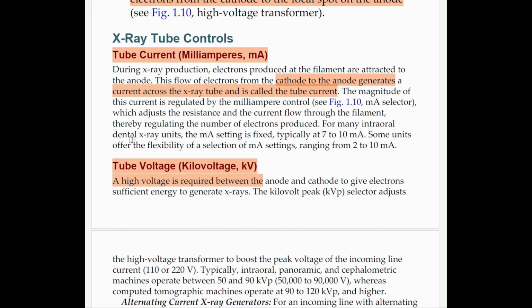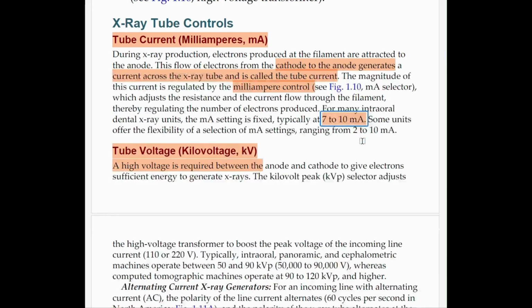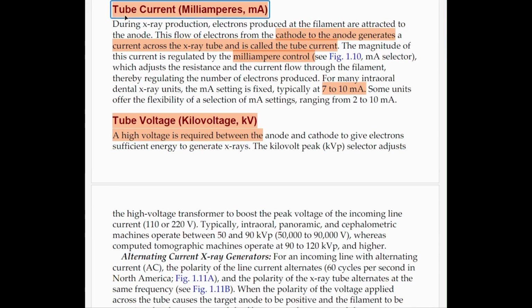The magnitude of this current is regulated by milliampere control. For many intraoral dental X-ray units, it is typically fixed to 7 to 10 milliampere. This is important. So, important things that you need to mention: 7 to 10 milliampere. And what is tube current?